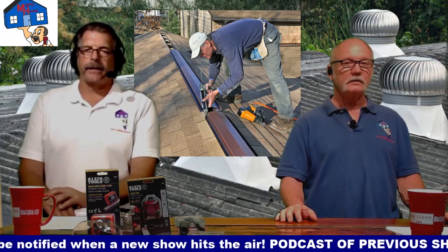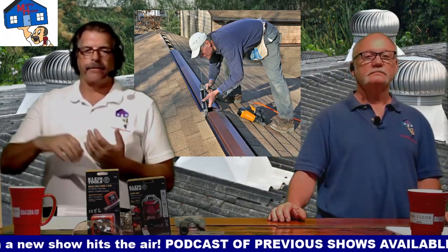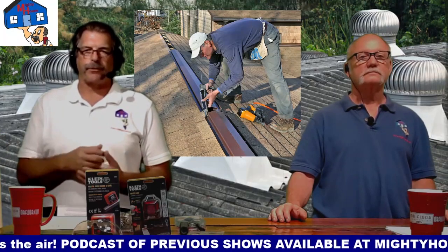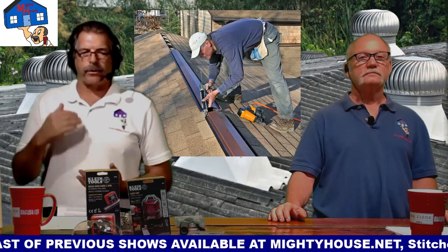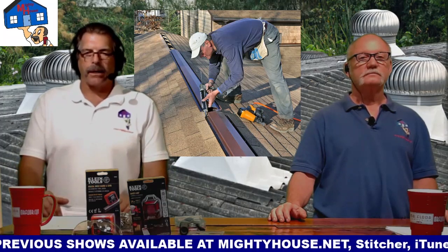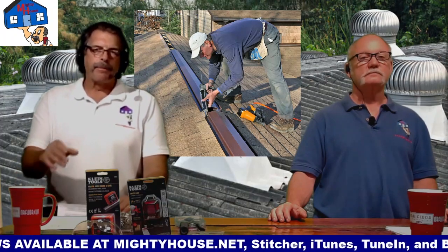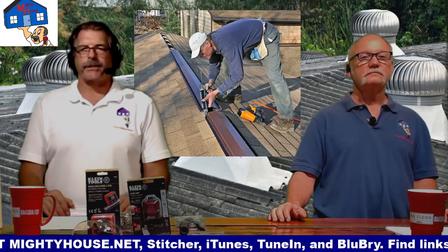Yep. Again, a real simple recap: if you have a non-vapor barrier ceiling, with lots of holes in it, you need 1 square foot for every 150 square feet of attic space. If it's a good sealed ceiling system with vapor barrier, then we want to go 1 square foot for every 300. So these are your roof venting options. And next week, we're going to talk about your soffit venting issues.